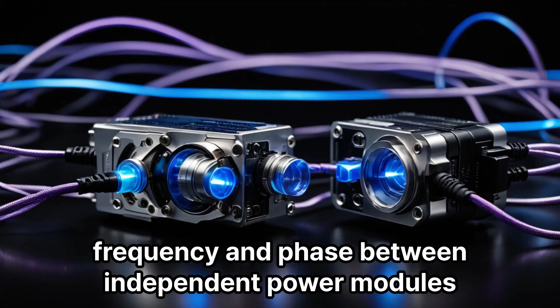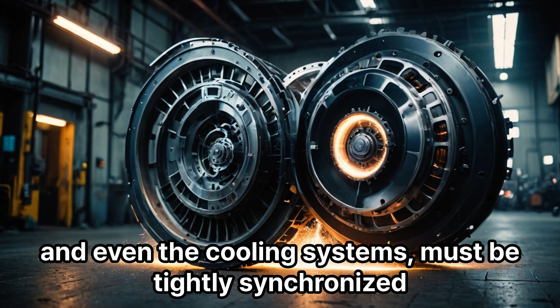The Resilience Blueprint for 2026 mandates a truly unified and intelligent ecosystem for emergency power. All components, from the individual UPS units to the static transfer switches, the generators, and even the cooling systems, must be tightly synchronized and seamlessly integrated to prioritize data integrity above mere system uptime. An infrastructure that is technically up, but whose data is compromised or corrupted, is, by definition, not truly resilient.